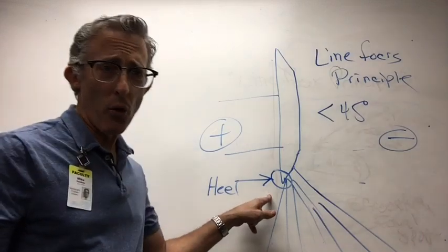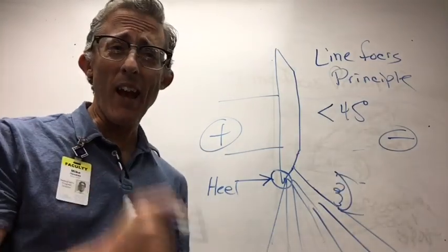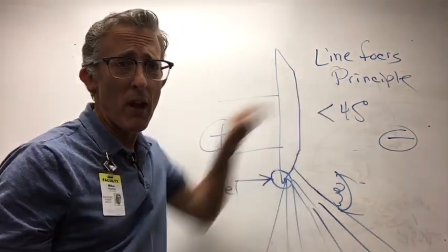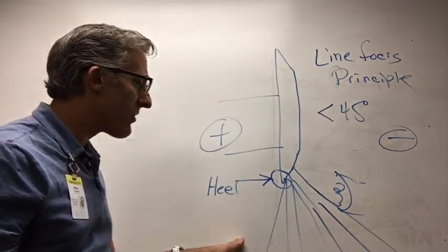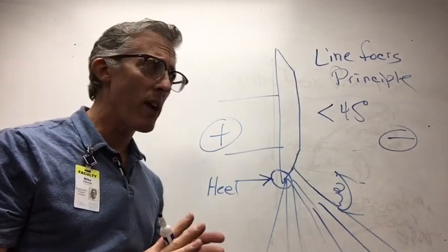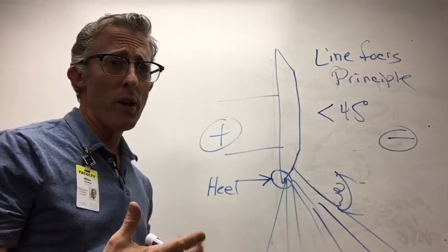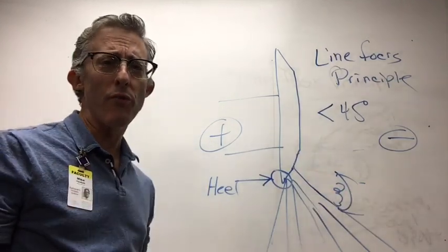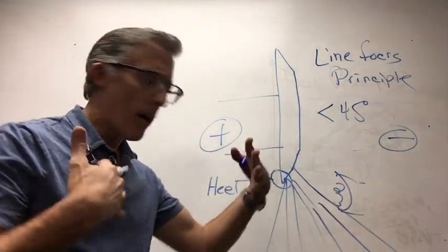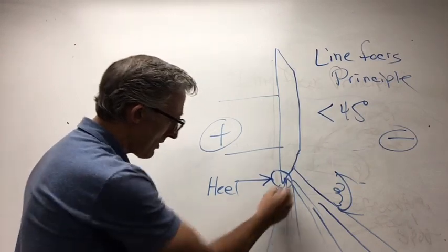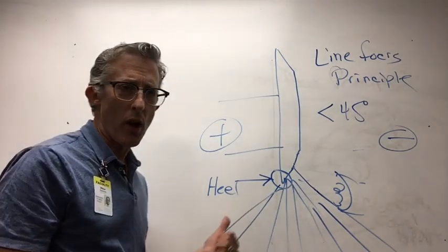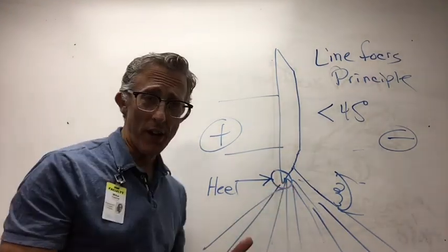The important thing to note about the anode heel effect, which again, is a byproduct and a symptom of the line focus principle, is that you're only going to notice the anode heel effect in any sort of measurable way when the collimators are opened all the way and you have a very, very large field size. And that is because as the collimators open up and your field size increases, it's going to be markedly clear that your intensity is dropping off on the anode side of the anode heel effect.